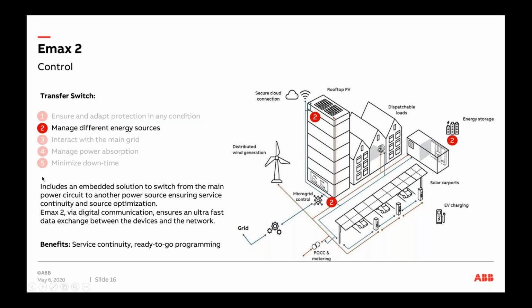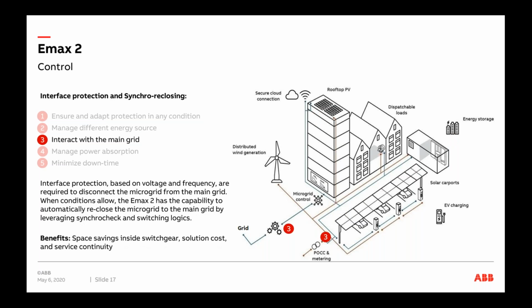Then we have interface protections. Now, this is mainly on reclosing. So when we are looking at going back to the main grid to supply, the synchronizing relay, which I just spoke about on the ATS setup or embedded ATS, uses the logic to sync both power supplies to ensure that we don't have any loss of time or downtime. That's a protection which can be a part of the Emax 2 setup as well.